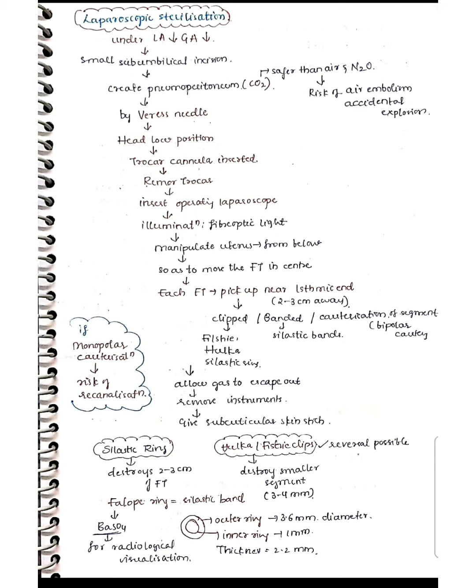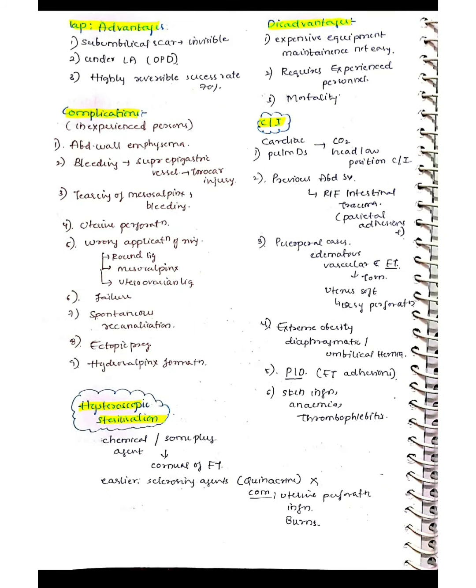The Silastic ring, also called the Falope ring, destroys two to three centimeters of the fallopian tube. It has an outer ring of 3.6 mm diameter, an inner ring of 1 mm diameter, and a thickness of 2.2 mm. It is impregnated with barium sulfate for radiological visualization. Hulka and Filshie clips destroy a smaller segment of 3 to 4 mm, making them potentially reversible, unlike the elastic ring.